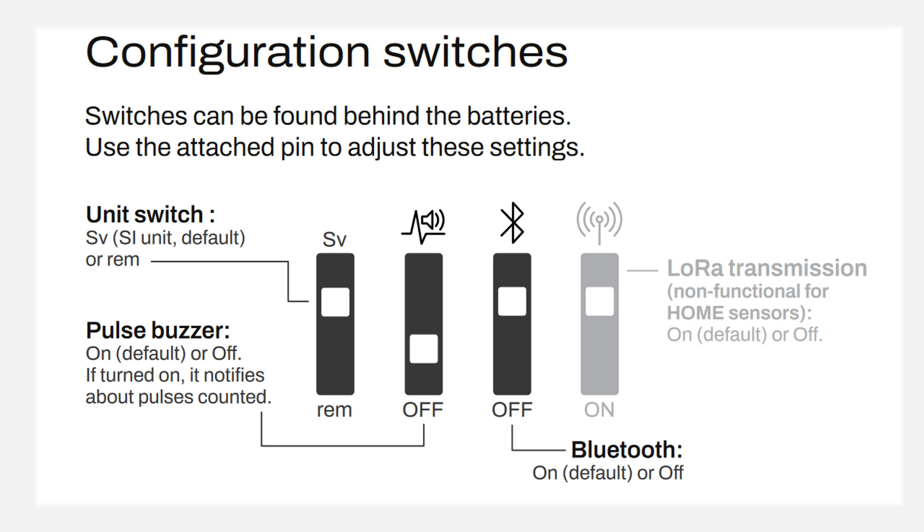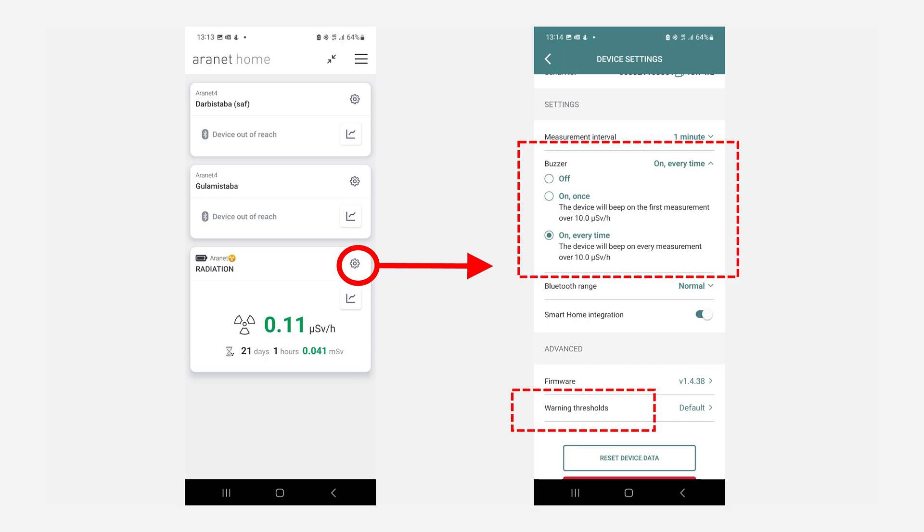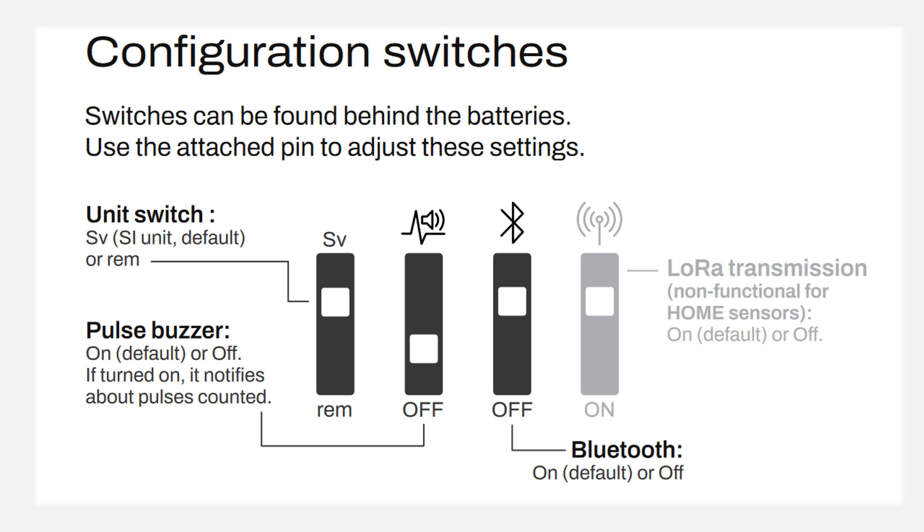So if you enable this functionality, each time your sensor beeps, a radioactive particle or radiation quantum has been registered. You can also enable an auditory signal to notify you when the safety threshold has been exceeded — this emits a slightly longer beep. This functionality can be enabled or disabled from the Aranet Home app, and the warning thresholds can also be edited there. The last DIP switch that may interest you is the third switch, which enables the Bluetooth signal.